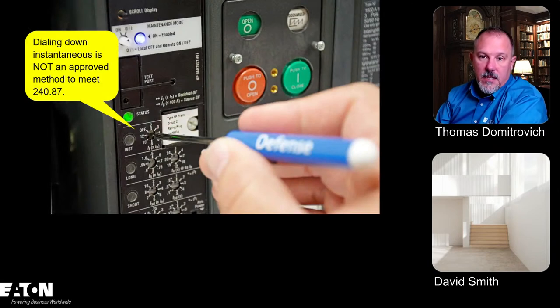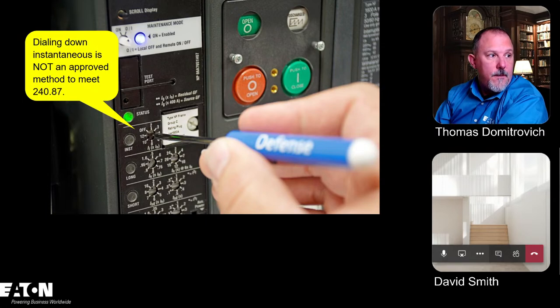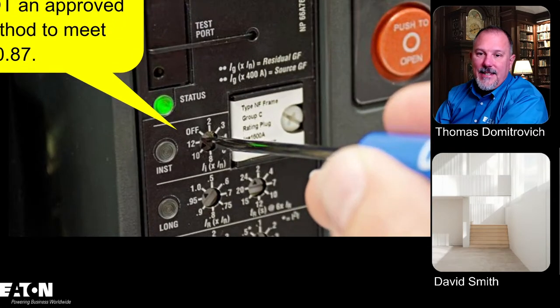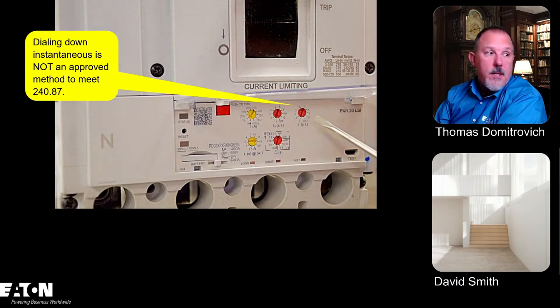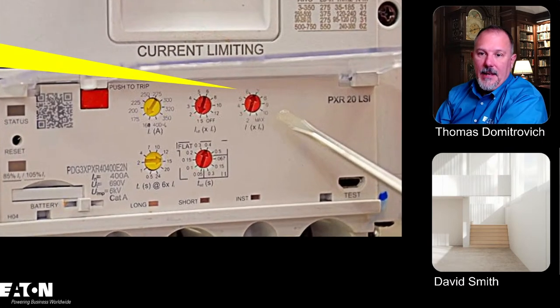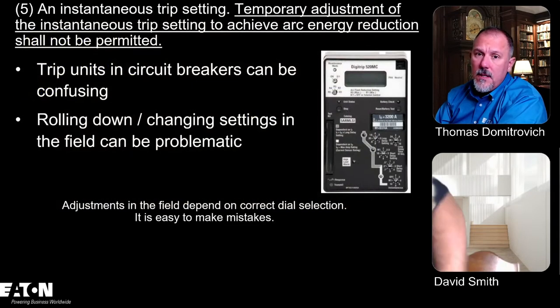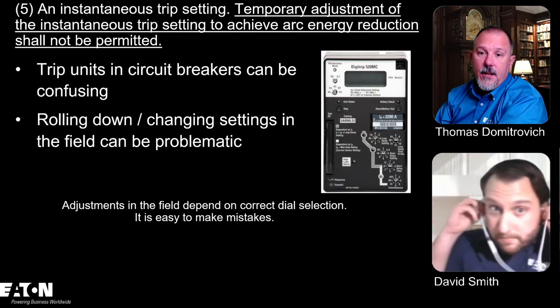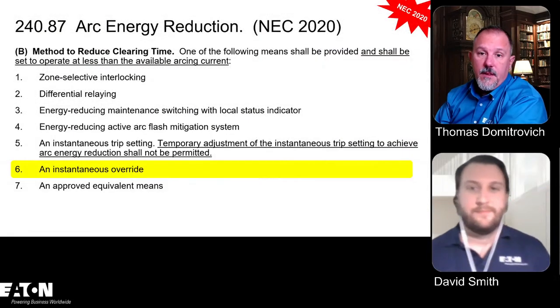You'll have some that look like this. This is really nice because it says INST, so you know that's the instantaneous, but that's just one manufacturer's way of doing it. Here's another one that says IN. Which one of these dials is instantaneous? It's not very clear. So how is an electrician in the field going to know which dial to turn to make sure they are adjusting the instantaneous down? It's for all of these reasons that code panel 10 said do not do any adjustments in the field.